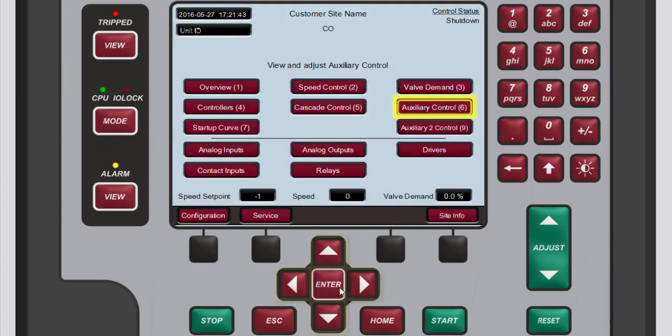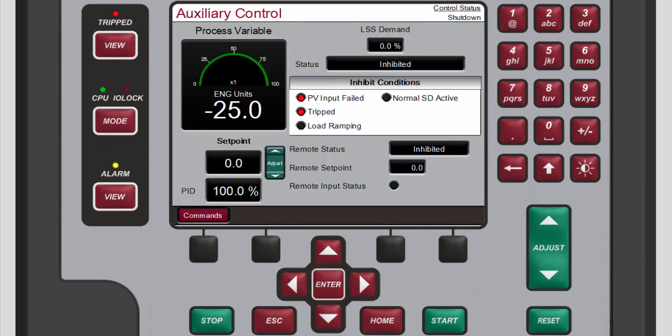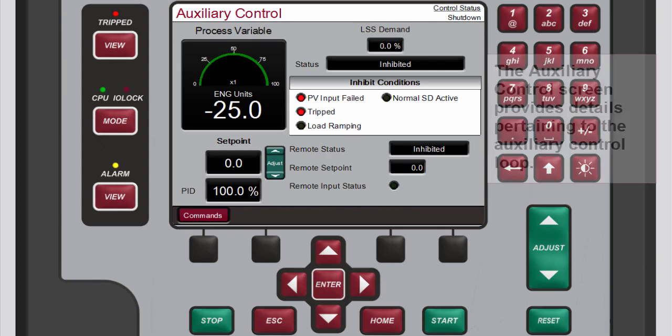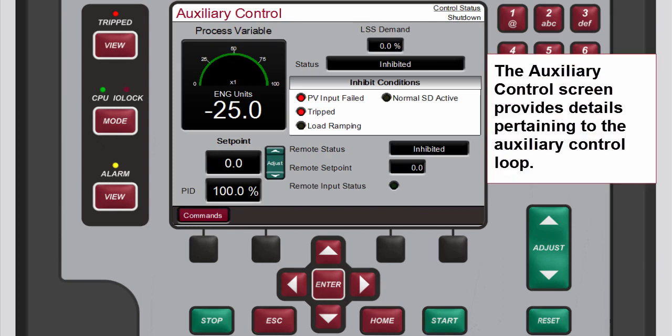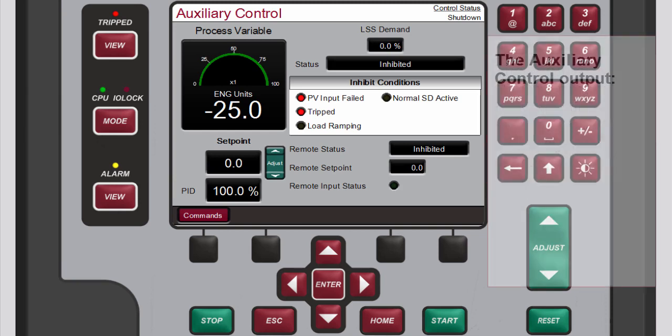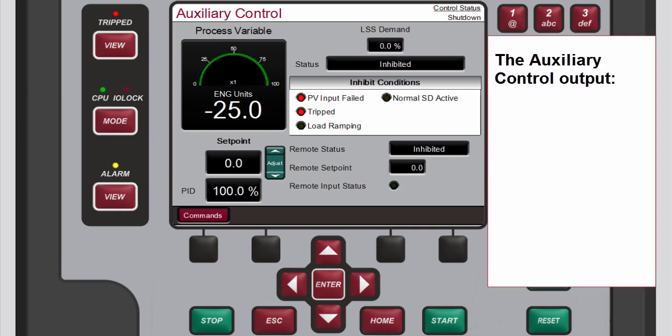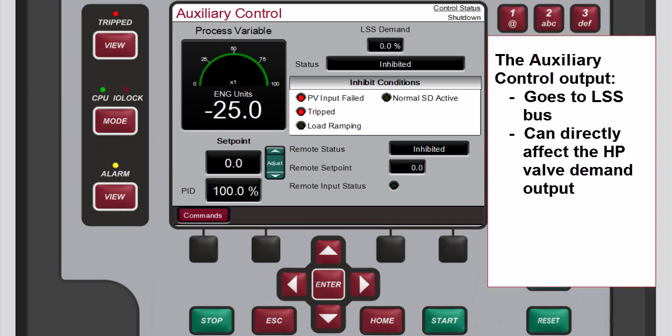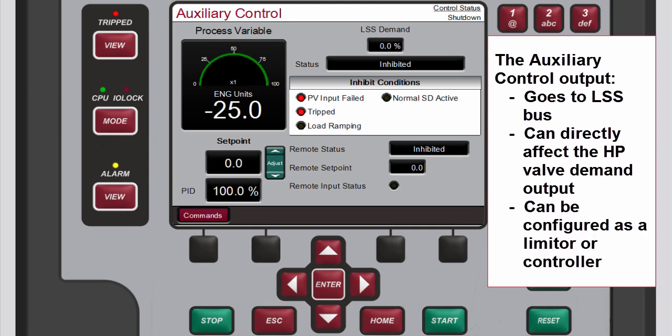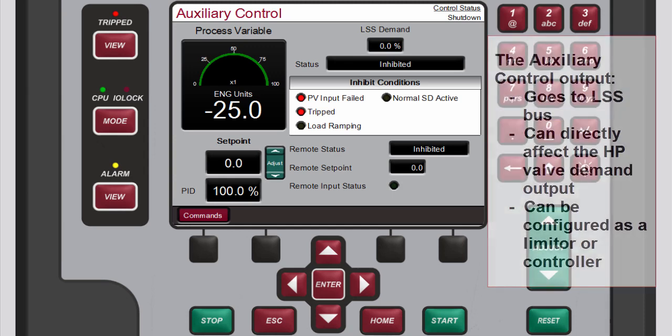The auxiliary control screen is available when the unit is configured for auxiliary control. This screen provides details related to the auxiliary control loop. The auxiliary control output goes to the LSS bus and can directly affect the HP valve demand output. This can be configured as a limiter or a controller.